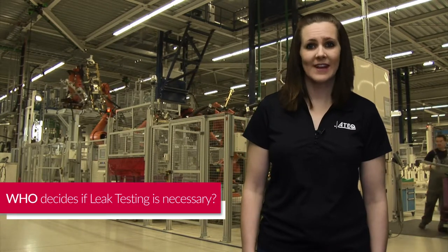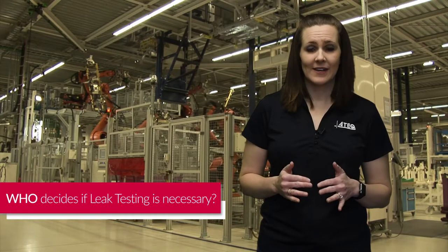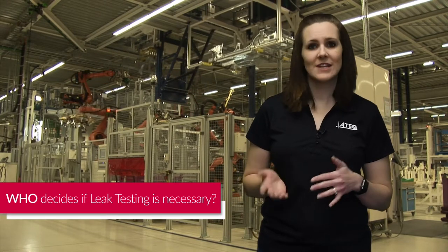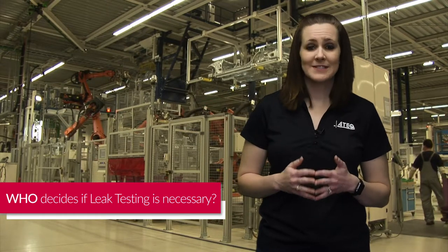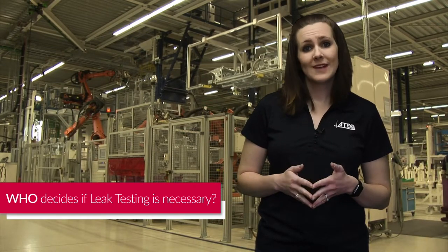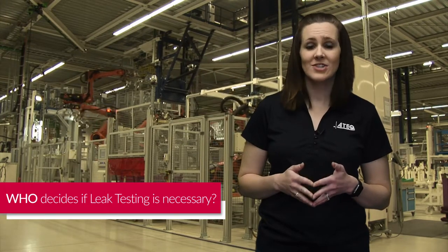Leak testing requirements are usually determined by manufacturing engineers. Once they determine that a product they will be manufacturing needs to be leak tested, those engineers work with ATEQ sales engineers to develop leak testing specifications to determine what type of leak testing will be best for the application and what the leak rate reject limit will be.